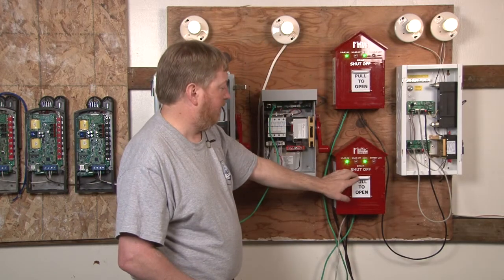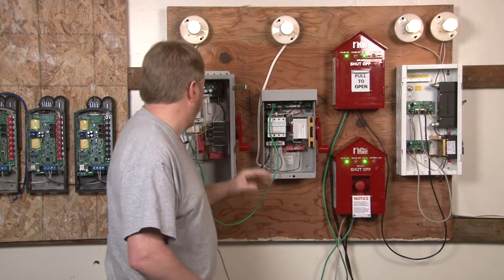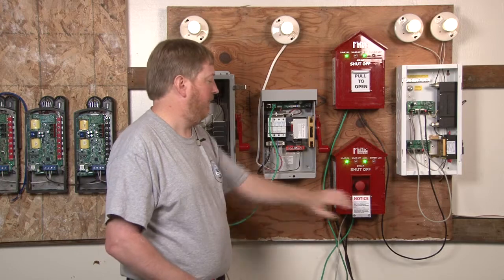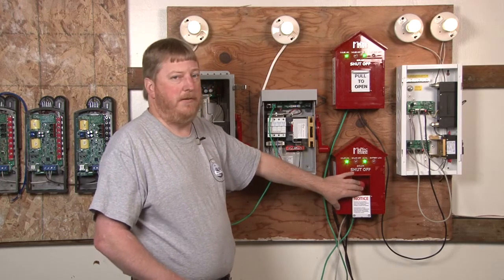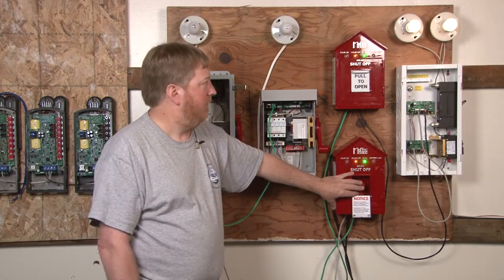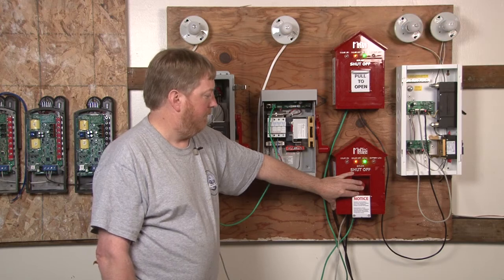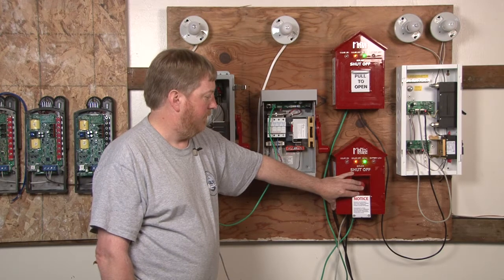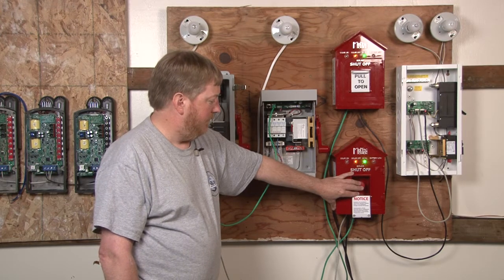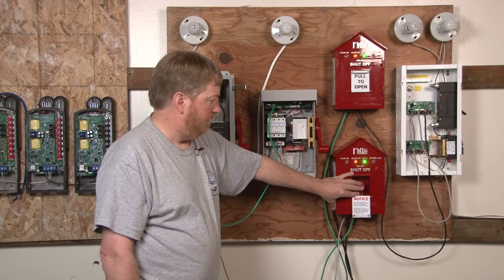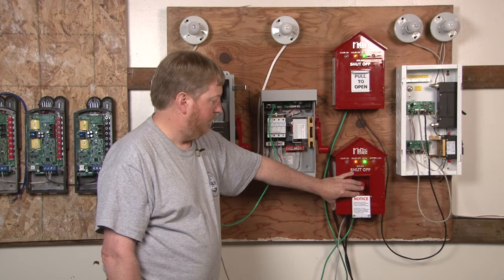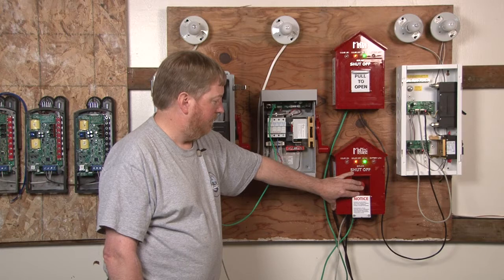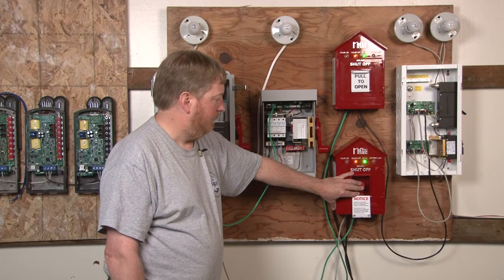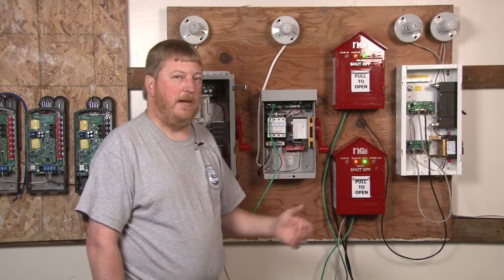So now I want to show what happens during the daytime. Sun is out, firefighters roll up, they hit the button. The combiner circuit breaker is open. There are still lethal voltages present between the solar panels and the combiner, which is a gray box with a red handle. Note that the handle will still be in the on position. However, the voltage is turned off internally. Okay, so that was the daytime announcement.